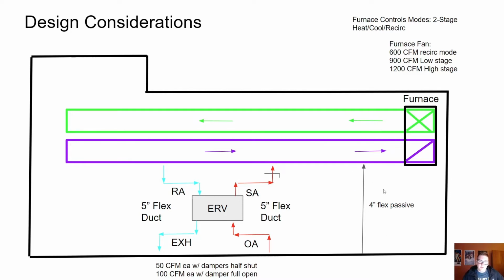I took out this 4-inch flex duct that was my passive ventilation and capped that on both the return duct and the outlet as well. And instead, I'm going to be using this ERV. Like I showed you, this design is for if you have an existing furnace that you want to tie into for the ERV. So let's say you built a new barndominium and you've got radiant floors for your heating and you don't need cooling, you just install the ERV standalone. But since I've got an already existing furnace, I wanted to tie into that and use that ductwork so I didn't have to run extra ductwork or things like that.